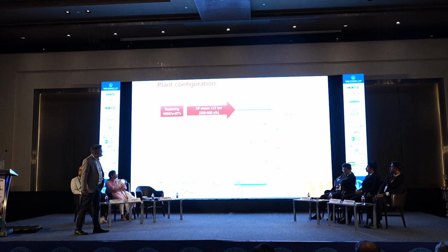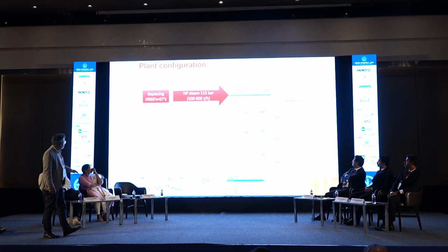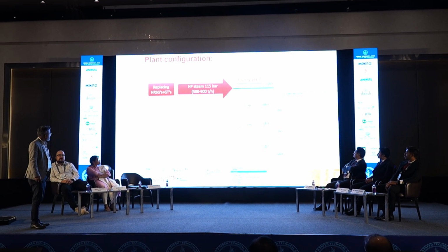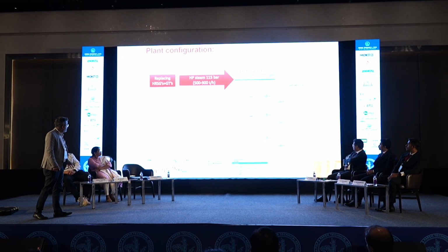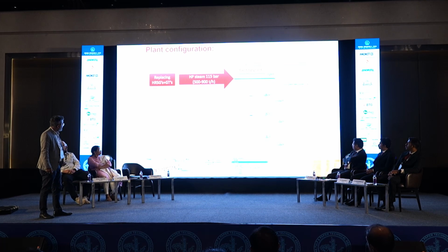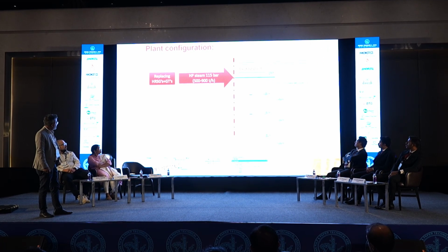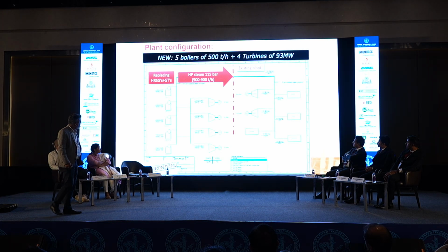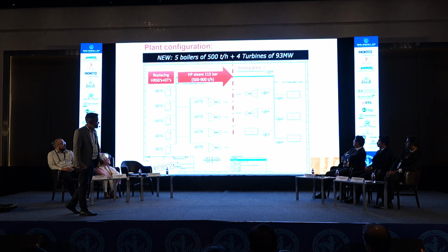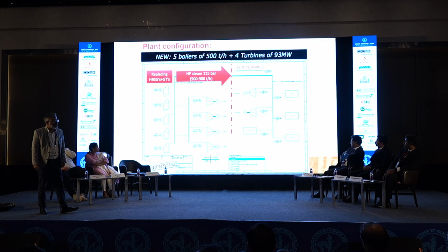This was their existing plant configuration where they had these GTs and HRSGs. Their HP header was 115 bar. The flow rate varies from 500 to 900 TPH, and they replaced it with 5 new CFBC boilers of 500 TPH each and 4 new turbines of 93 megawatt each.